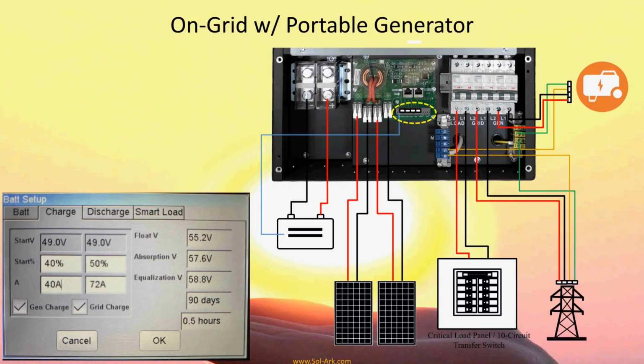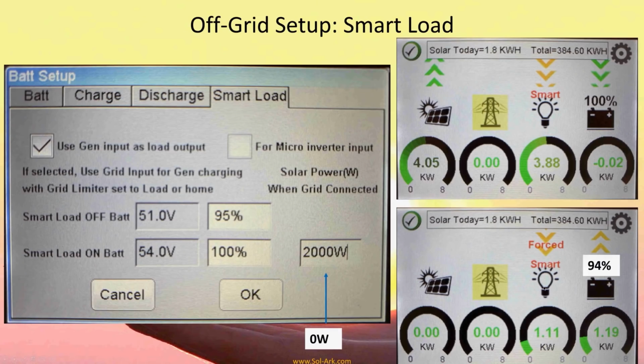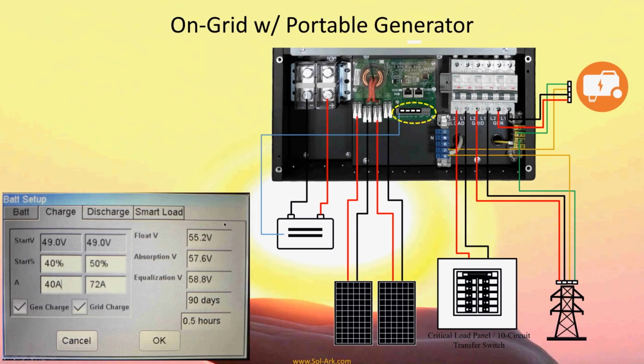Someone asked for a long press. If, let's say, my batteries are below where the smart load will turn on, let's say my battery bank is down around 90%, instead of changing the programming settings here, I can just press and hold this load icon. It will force the smart load on, and then 4 hours later, it will automatically go back to its normal cycle. That's what that question was about.